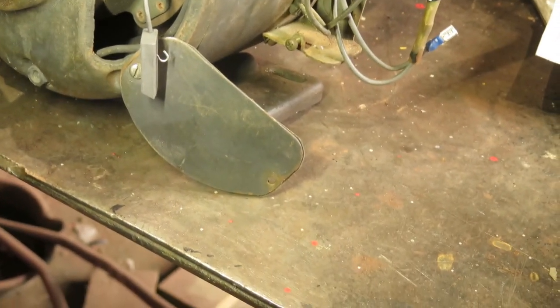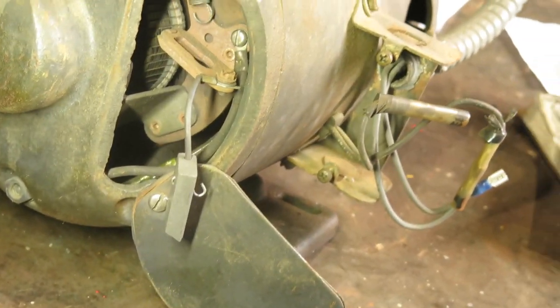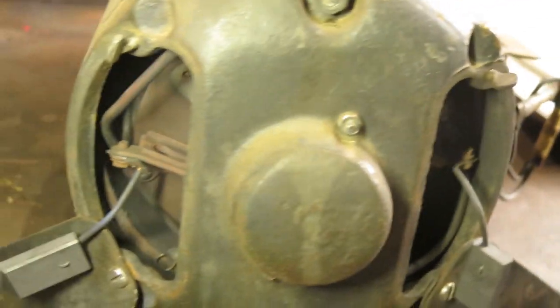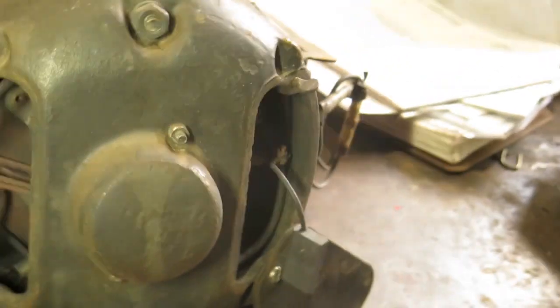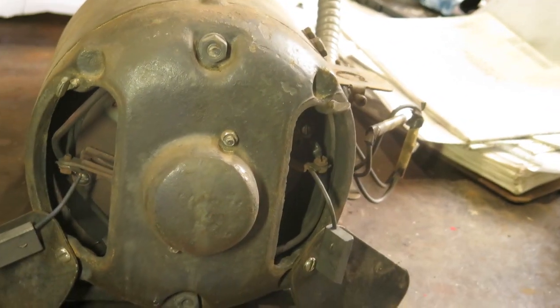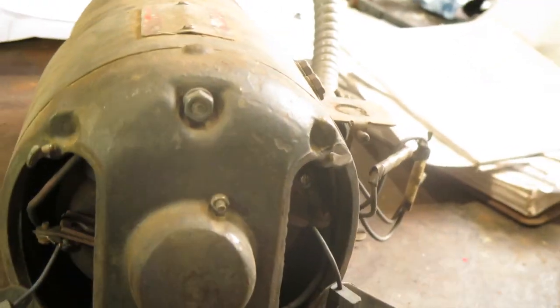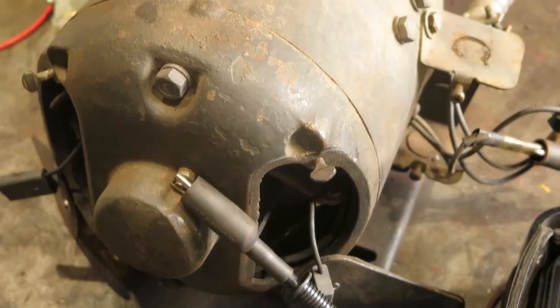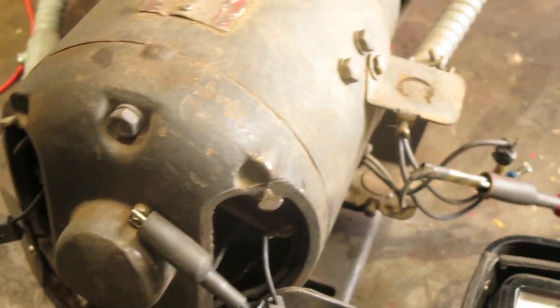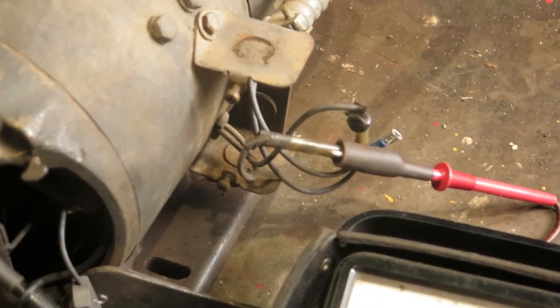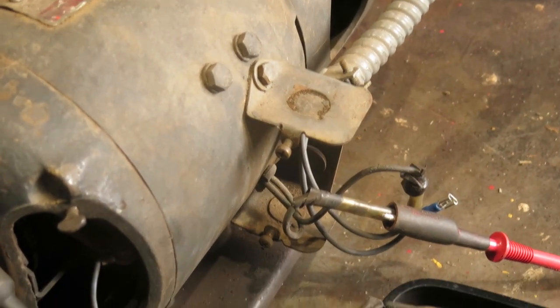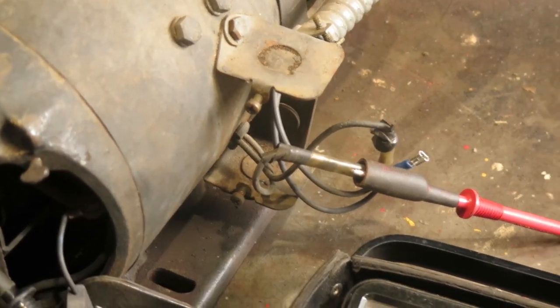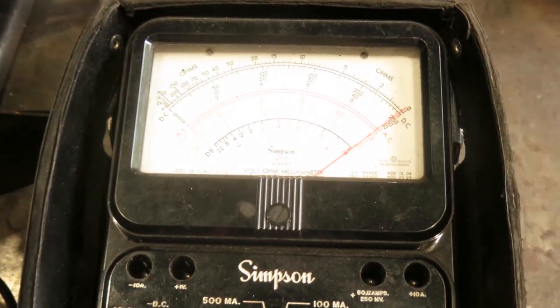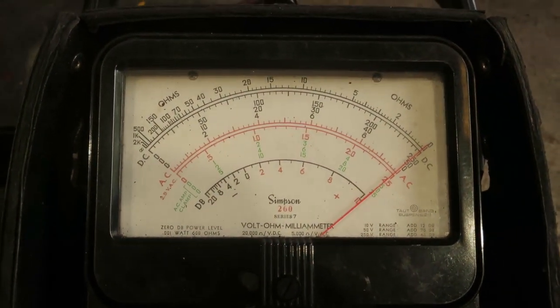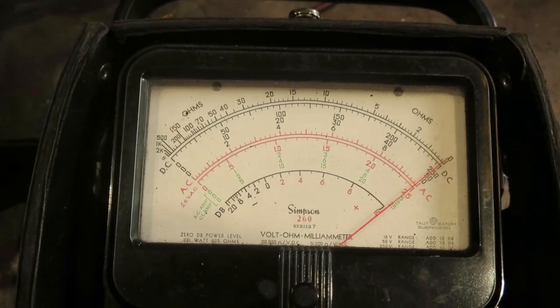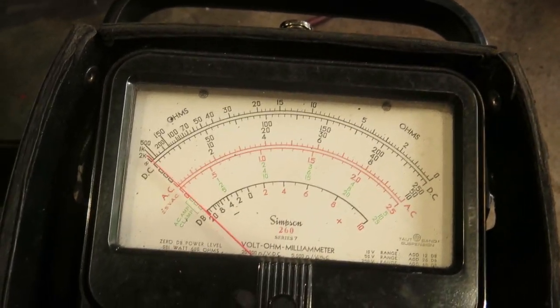The next step is to pull the brushes out. There's one brush hanging loose, and there's the other brush hanging loose, and that isolates the commutator of the motor from the frame. And check again. So connect the meter to ground, connect the other end of the meter to the negative wire that goes into the frame of the fuel pump motor, and we have 0 ohms. So just so you can see, we disconnect the ground and it goes away.